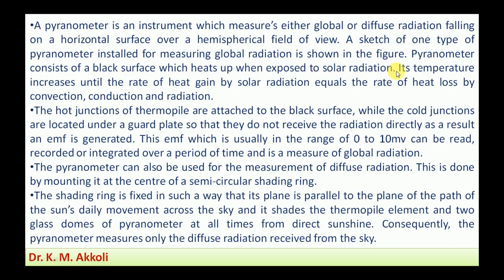The black surface heats up when exposed to solar radiation; its temperature increases until the rate of heat given by solar radiation equals the rate of heat lost by conduction and radiation. The hot junctions of the thermopile are attached to the black surface, while the cold junctions are located under the guard plate so that they do not receive radiation directly. As a result, an EMF — electromotive force — is generated between the hot and cold junctions.